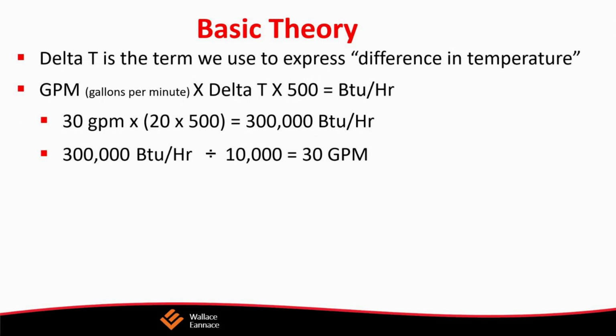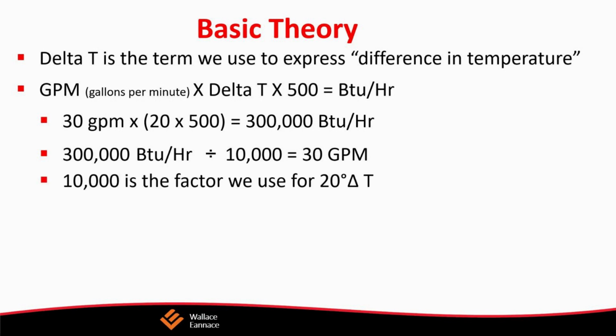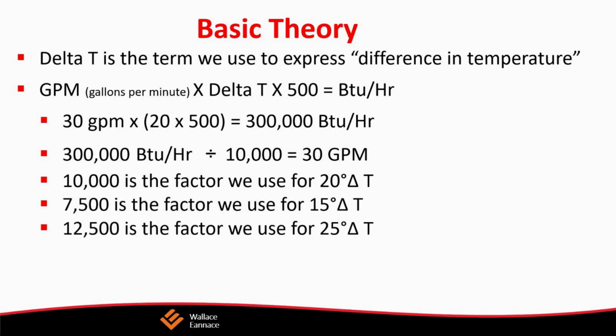So 1 gallon of water weighs about 8.33 pounds. And to get BTU from that information, we usually deal with BTUs per hour. So 8.33 times 60 minutes gives us 499.8, which we're going to round off to 500. We're going to be using this 500 a lot on the next few slides, so you can understand where that came from. The gallons per minute times the change in temperature, called the delta T, times 500 will give us the BTUs per hour.